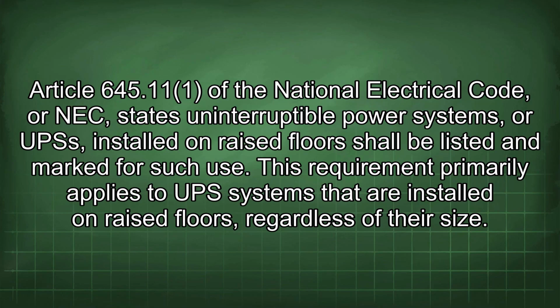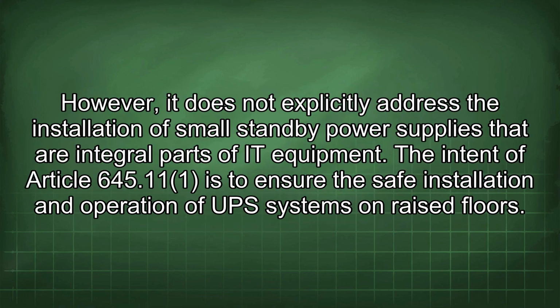Article 645.11 of the National Electrical Code, or NEC, states uninterruptible power systems, or UPSs, installed on raised floors shall be listed and marked for such use. This requirement primarily applies to UPS systems that are installed on raised floors, regardless of their size. However, it does not explicitly address the installation of small standby power supplies that are integral parts of IT equipment.